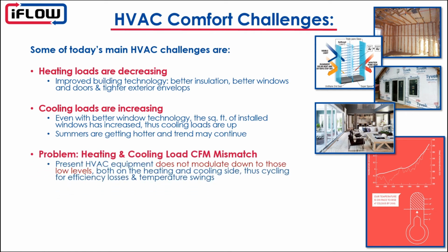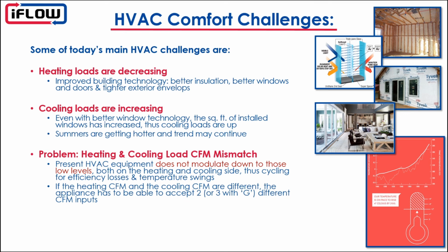So we have a problem with the heating and the cooling loads. We saw from the equipment side that we just went through, whether it's on the AC side or on the heating side, we have a problem in that the equipment is not matching the loads. The loads are going down or up, and the cooling and heating equipment are not able to deliver efficiently at those lower or higher ranges. That also leads to different CFM rates. The heating CFM rate might be at one level, and then the cooling CFMs might be different. And then if we have a circulation call, we may want that at even a different CFM level. So do the controls for this equipment have the ability to input 2 or 3 different CFM numbers?